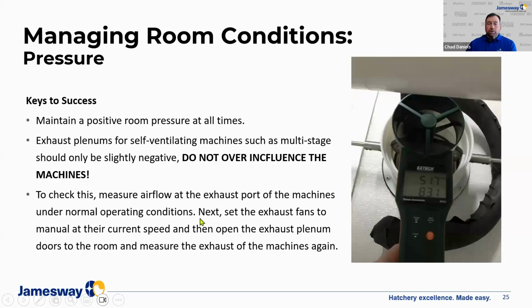It's pretty simple to take a measurement under normal operating conditions, and then set the equipment in manual so it's fixed operating, and take all the pressure off the plenum by opening the doors back to the room. Now I take that measurement again. I don't want to see a change of more than 10%, meaning I don't want to over-influence the machine. If my plenum is too negative, you'll have a much greater airflow when the plenum is operating normally versus when you take the pressure off of the machine. That's just a quick check to make sure you're not over-influencing self-ventilating machines.